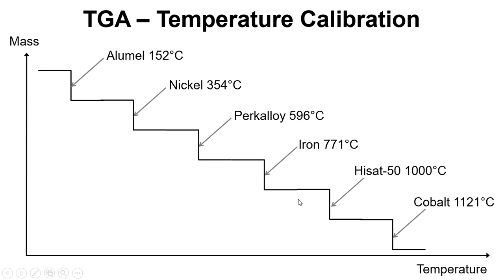If we have several standards, then we can measure and calibrate temperature over a whole range for the temperature that the instrument is working over.